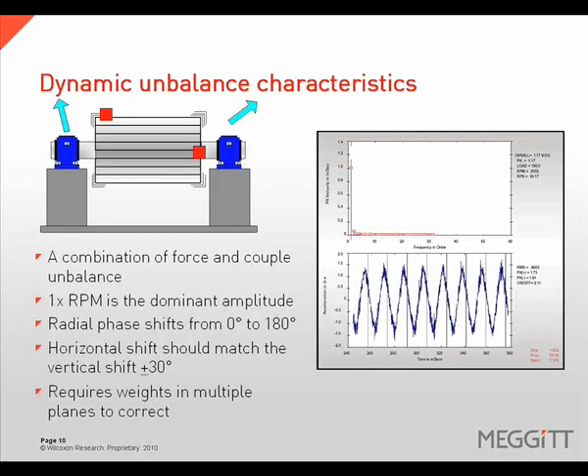Dynamic unbalance is a combination of force unbalance and couple unbalance. The dominant vibration amplitudes will occur at 1 times rotational speed. Radial phase readings will be unsteady from 0 to 180 degrees. The horizontal phase shift should match the vertical phase shift. Dynamic unbalance will require a multi-plane balance weight placement to correct.